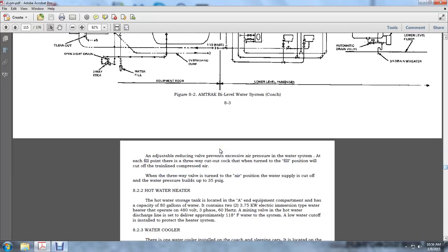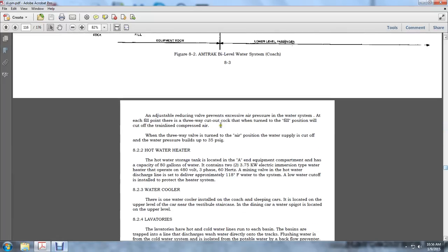An adjustable reducing valve prevents excessive air pressure to the water system at the fill point of the three-way cock. Turning the fill position off will cut off the train's compressed air. When the three-way valve is turned to the air position, the water supply is cut off and the water pressure builds up to 35 psig.